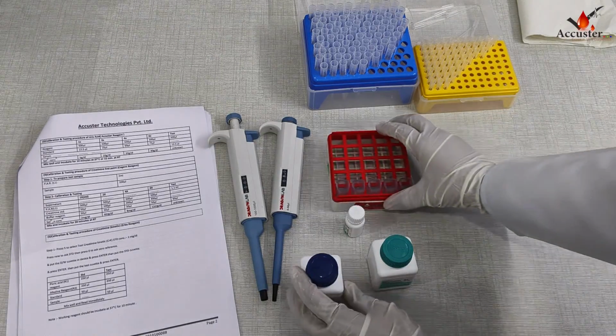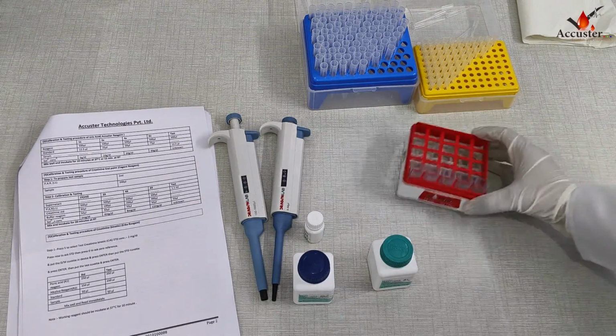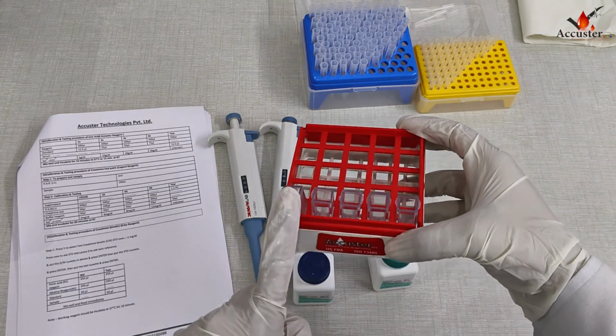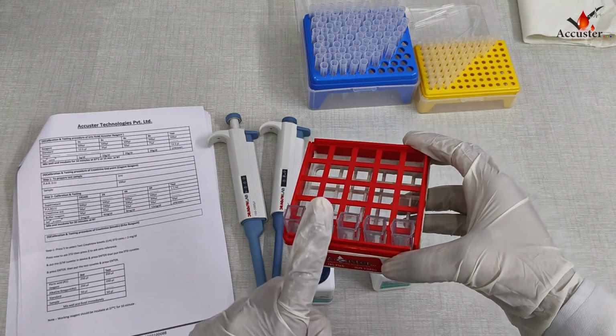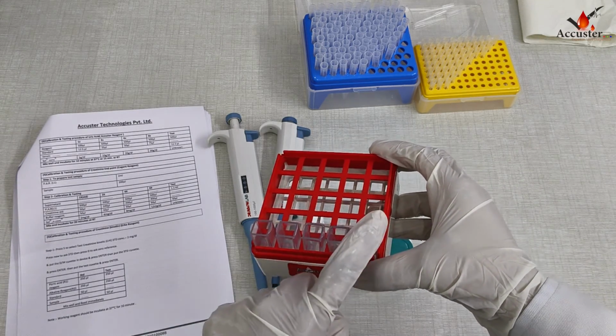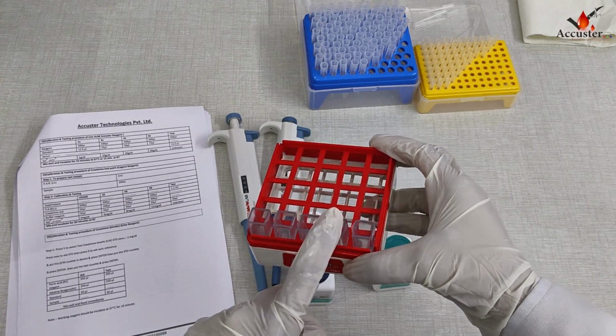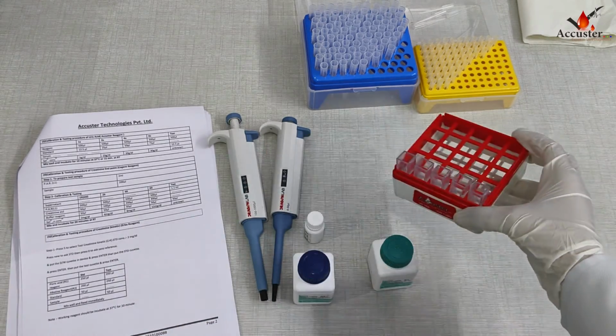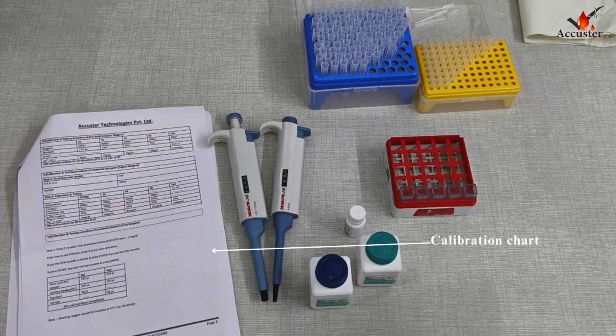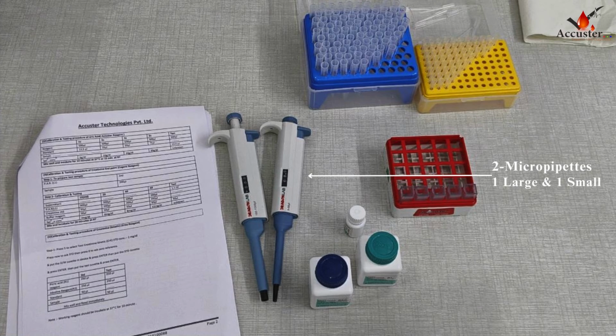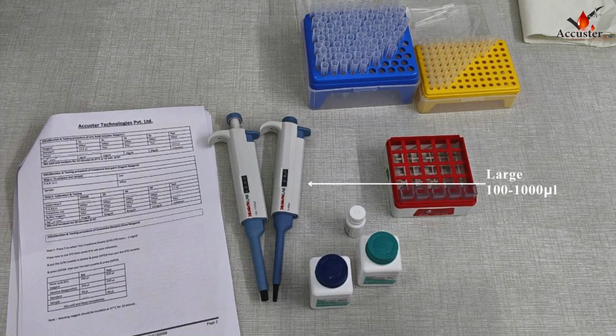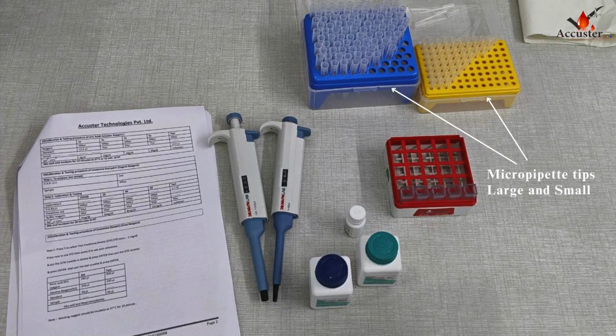For calibration, we need 3 clean dry cuvettes, one each for standard, L1 and L2, and 2 more cuvettes for samples, as we have 2 patient samples. Calibration chart: 2 micropipettes, one large and one small. Large of 100 to 1000 microliters and small of 5 to 50 microliters. Micropipette tips, both large and small, and tissue paper.